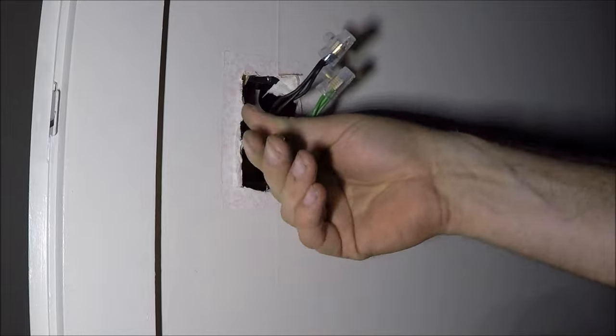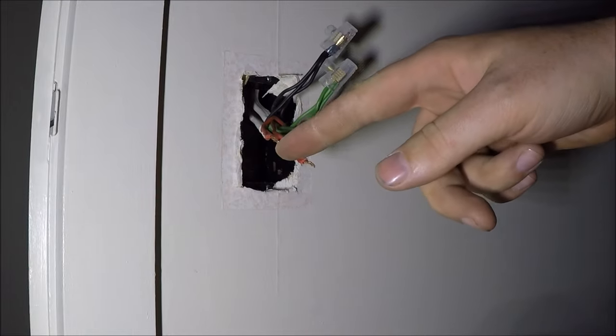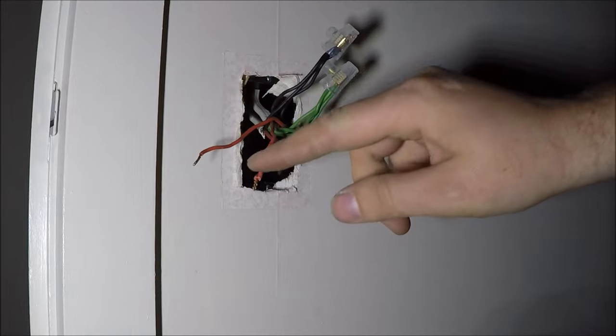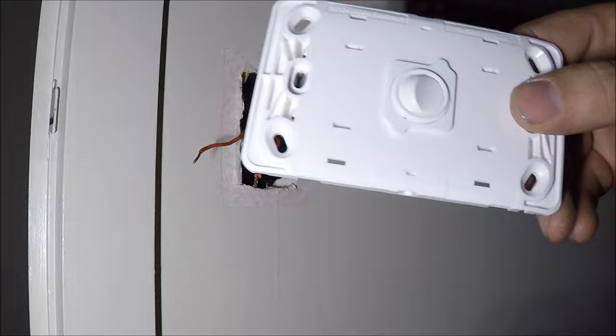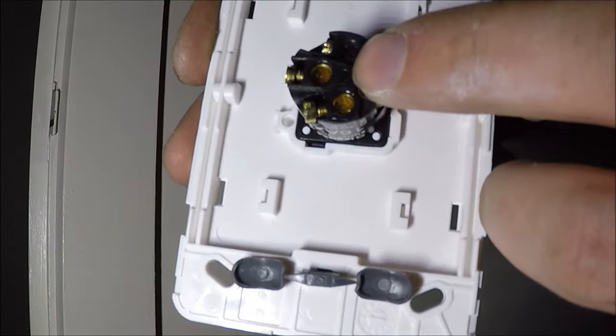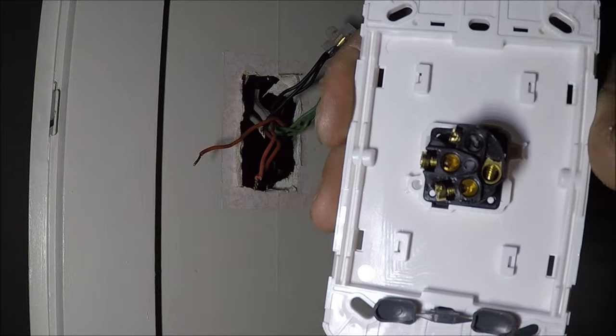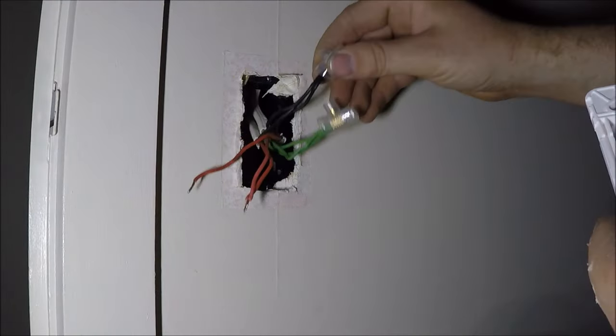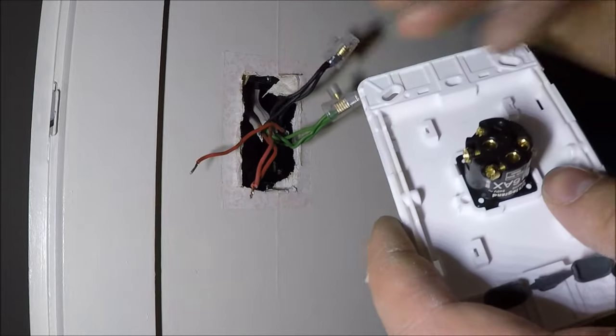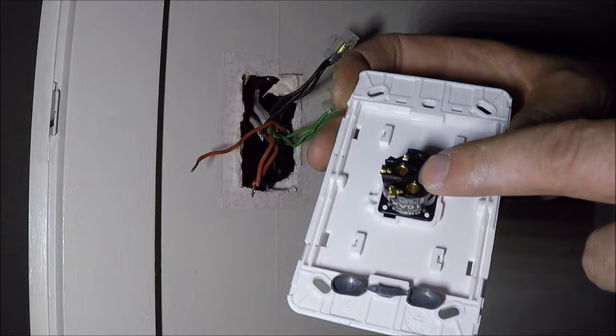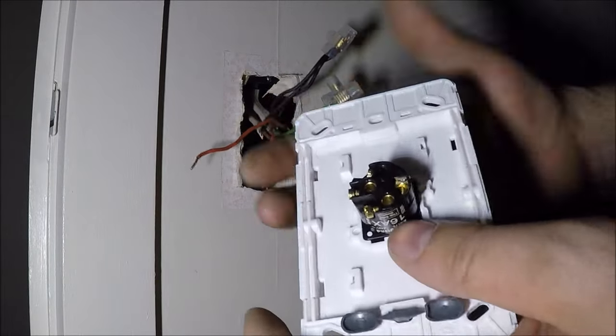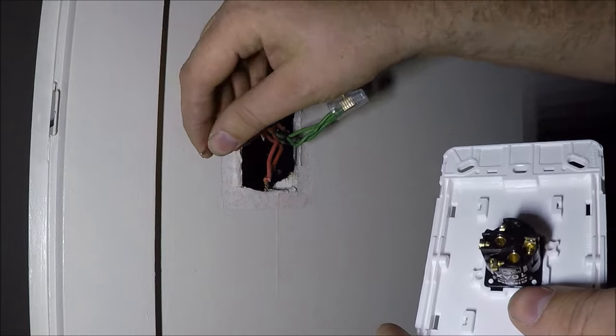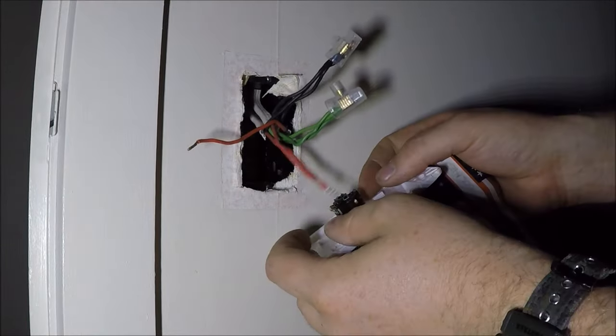Right, now we're left with our feeds and our light switch cable. So our feeds here will be going into the C of the new switch. So on the back of here we've got one, C, two and loop. Don't worry about the two, we're not doing two-way switching. The loop terminal here acts just like one of these connectors. It's completely separate from the switch itself. So our C is the common for the feeds. So these two twisted up will be going into the C, and then this one going into the light will be going into the one. So I'm going to fit that off right now.